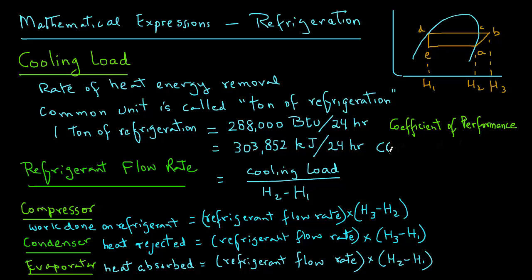COP equals H2 minus H1 divided by H3 minus H2. Note that H2 minus H1 is the section that represents how much heat is absorbed by the refrigerant. H3 minus H2 represents the amount of work done by the compressor on the refrigerant.